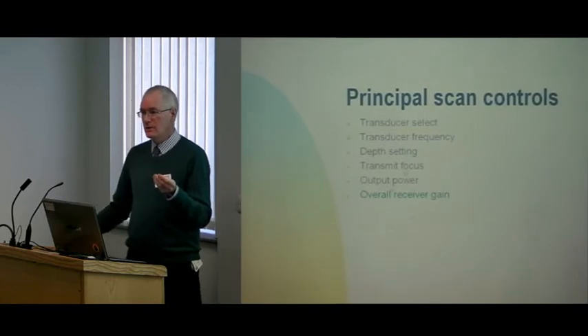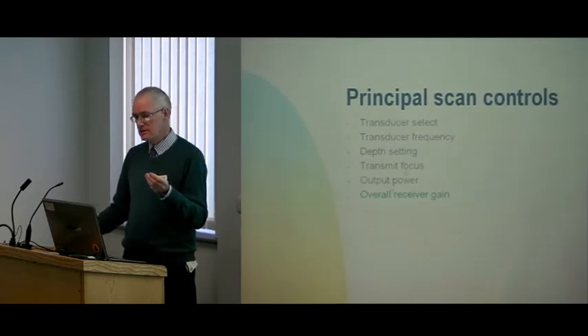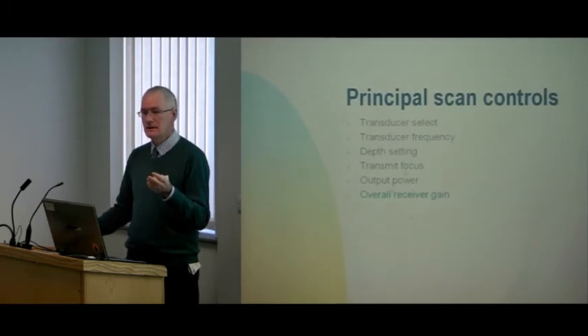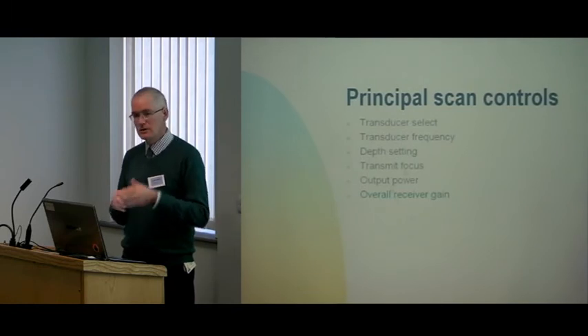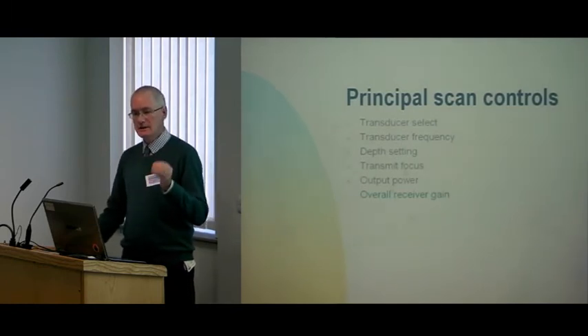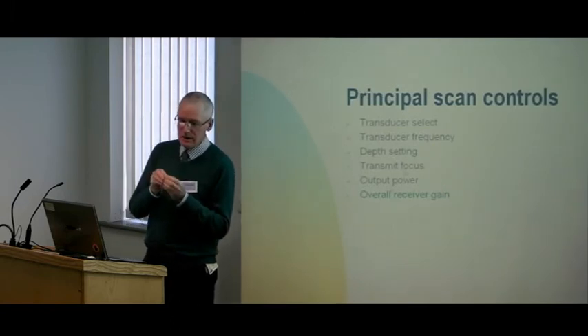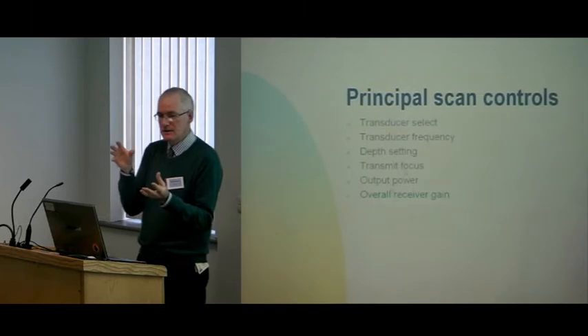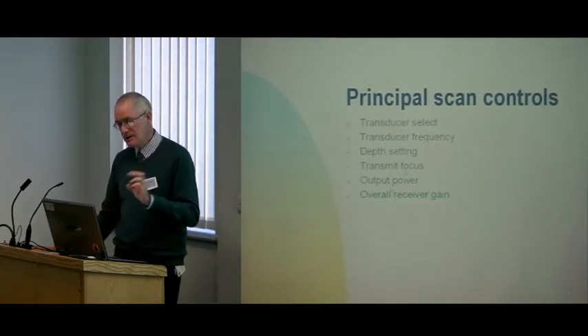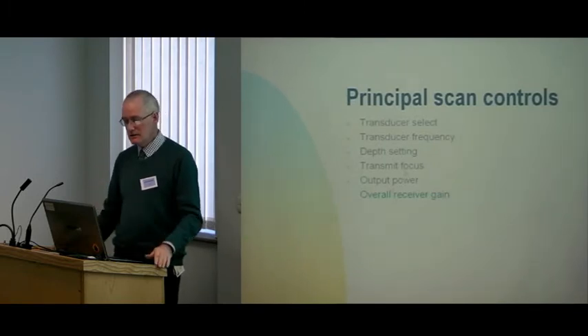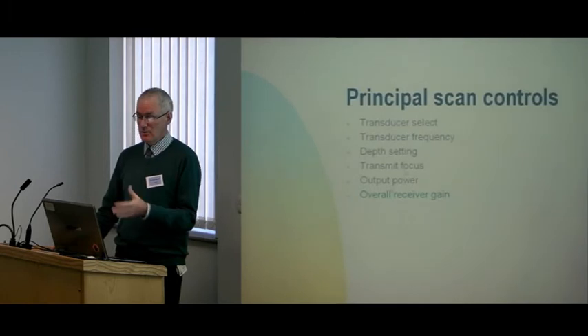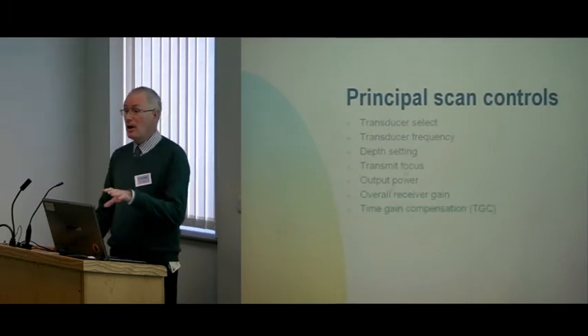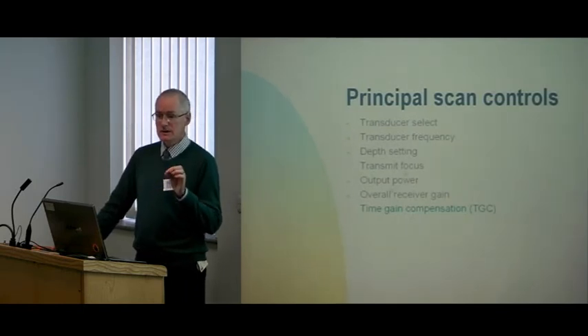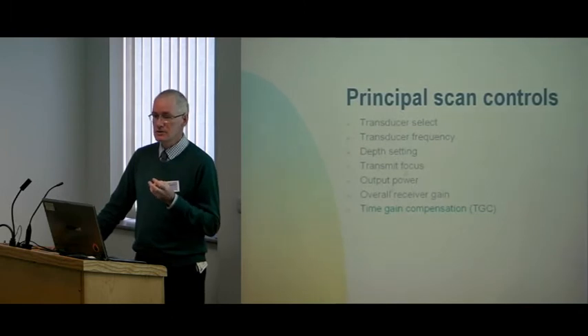It's not just thermal energy, the thermal index that we need to talk about in safety terms, but it's also the mechanical energy, the mechanical index. There are these indices the industry uses to show you how safe you are using your machine. If you put a sound beam into a patient and you produce cavitation, then you explode a bubble of gas within tissue, which then collapses very quickly, and on collapse the deformity of tissues is really quite severe, and you can actually damage tissue if you have an inappropriately set up machine. It's never going to happen in your department, I don't think, but you need to understand that there are safety things, which are mechanical and thermal in the machine, mechanical index, thermal index, which will be set for you by the manufacturer.